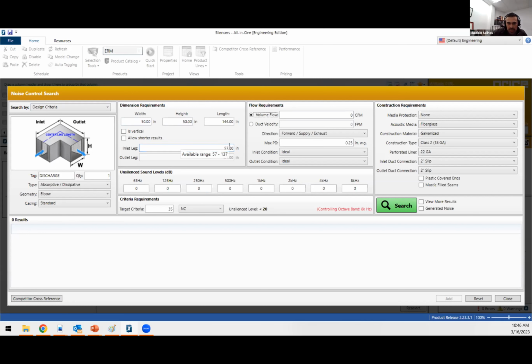Now you don't have to think about it. If you scroll your mouse, it's going to tell you the minimum leg length you could do for that width of silencer. And because you're fixing your center line length, it's going to automatically size the outlet leg of that elbow silencer. Every time you see a specification for an elbow, the length that they specify is the center line length. It's not the inlet outer leg plus the outlet outer leg dimensions added together. So have that in mind.